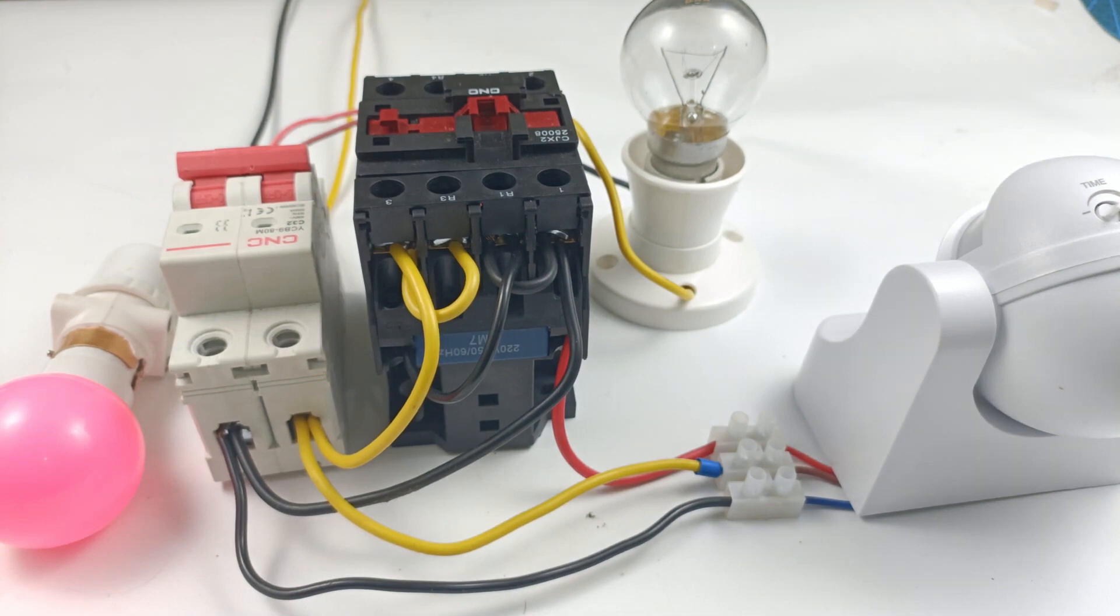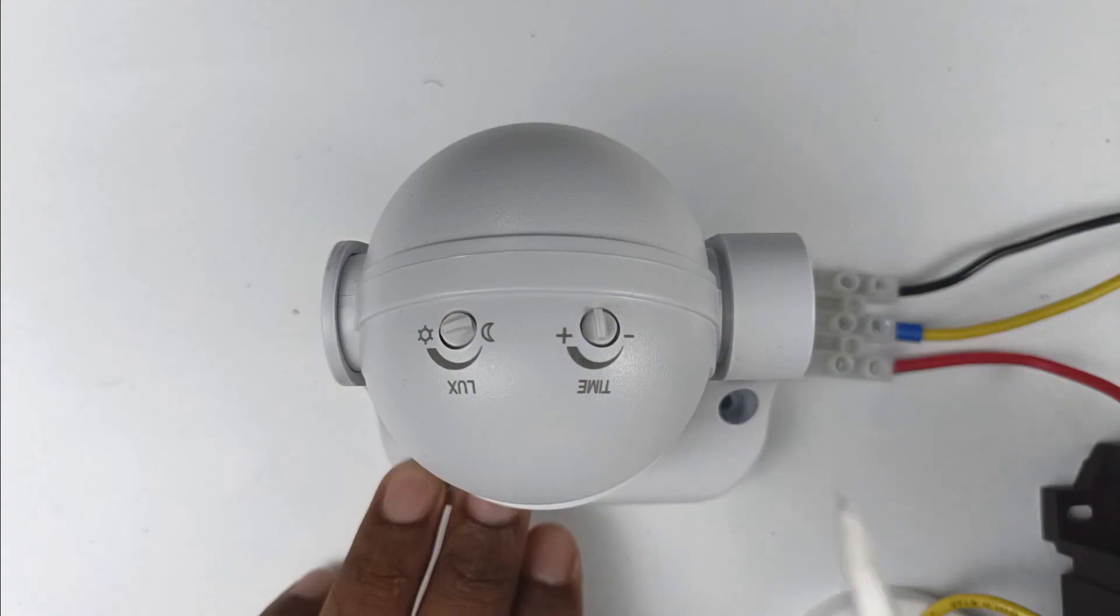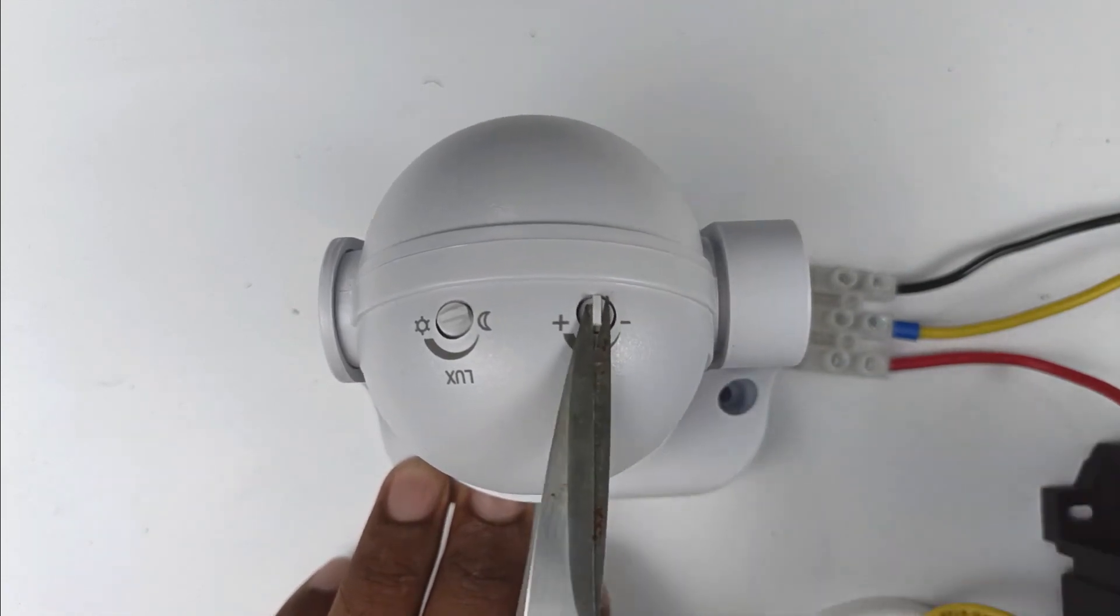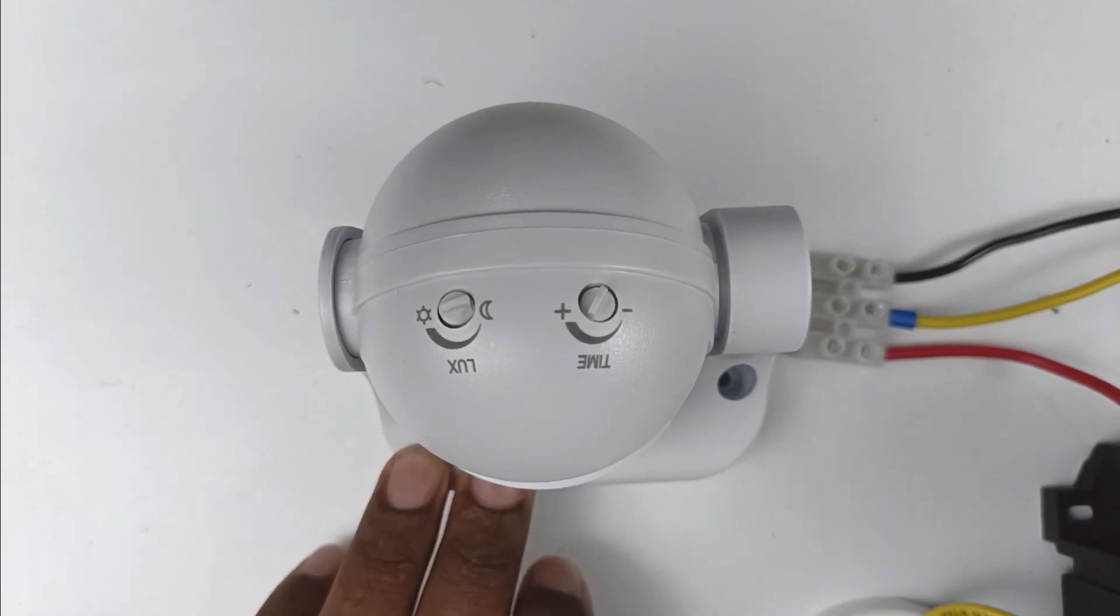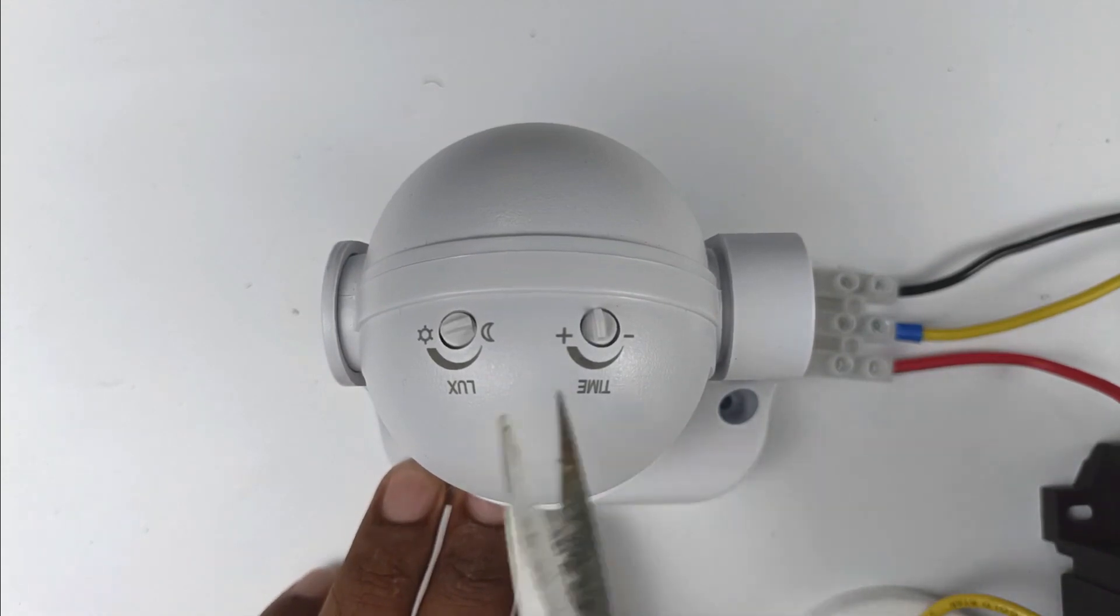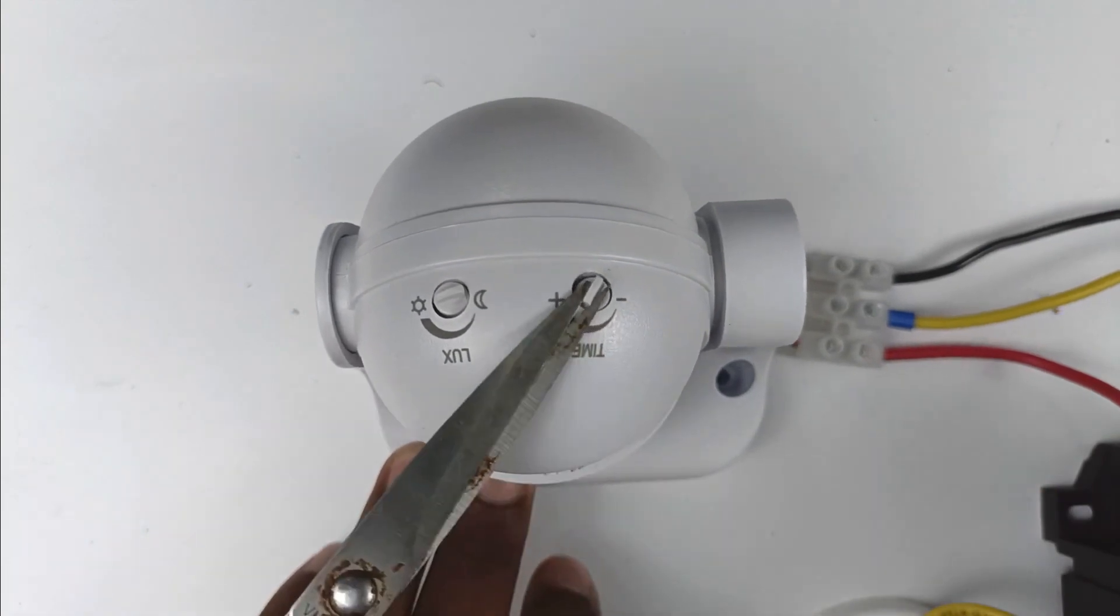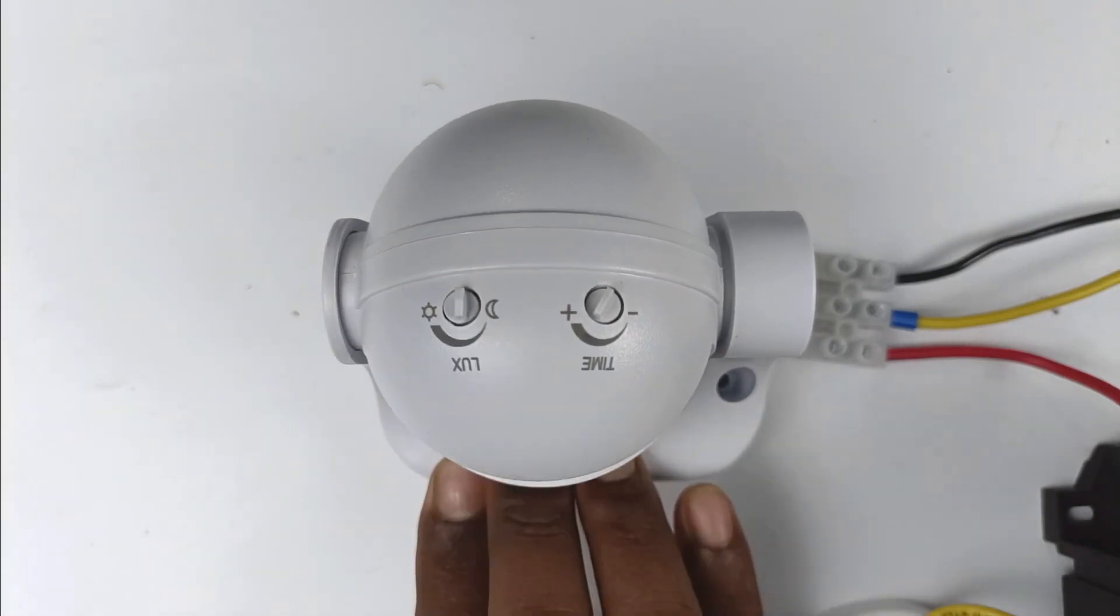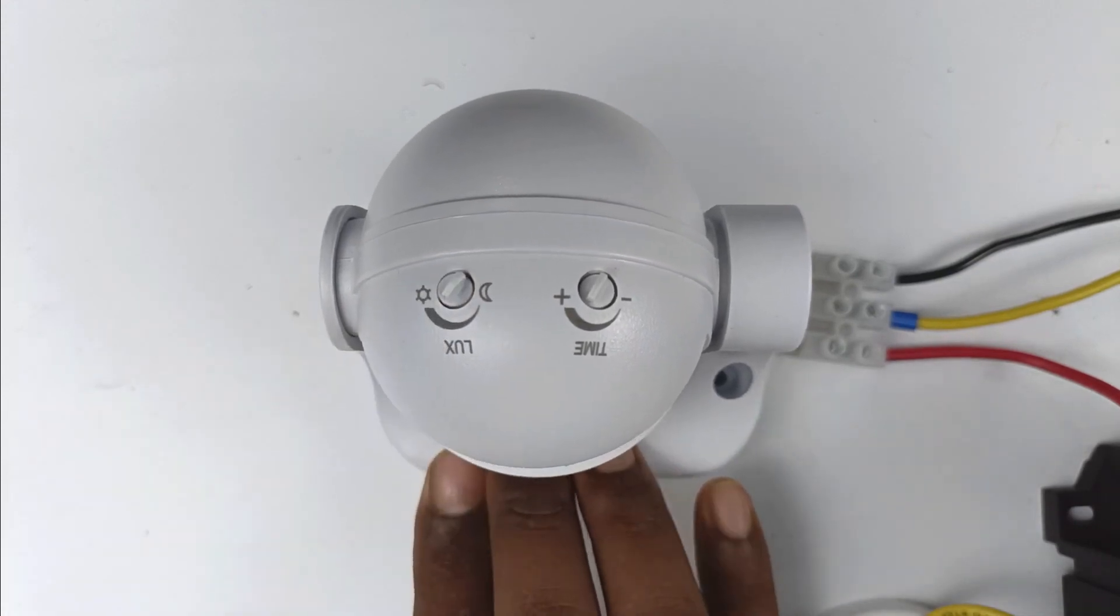So only this much connection is required. On this motion sensor I have, you can see two switches are provided. This first switch is for time delay. It means when target comes in front of the sensor and goes away, then till how much time motion sensor generates output supply, you can set this time by this switch. This means you can say that a timer is given here. How much time you want to set, you can set here by rotating the knob. Apart from this, one more switch is provided here. Through this, you can control the lux level. It means at how much brightness this motion sensor should be operated, you can do the programming through this switch here.